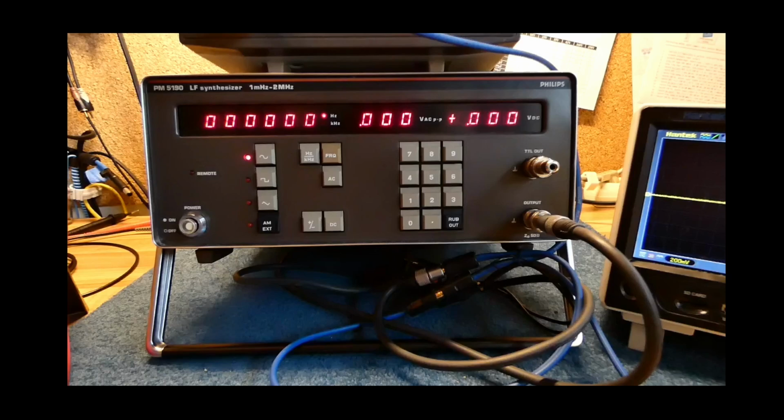On the left you can see select buttons for 3 waveforms: sine, pulse and sawtooth. You can select that and you can enter the frequency, and you can enter the amplitude, and the third option is you can also enter a DC offset. So you can have, for instance, a 1 volt DC offset.